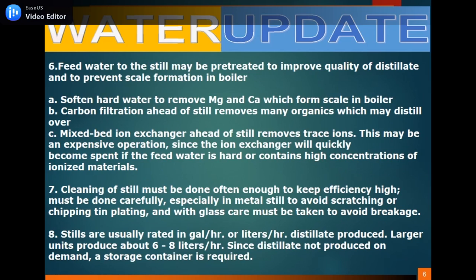Feed water to the still may be pre-treated to improve the quality of the distillate and to prevent scale formation in the boiler. Hard water should be softened to remove magnesium and calcium, which form scale in the boiler. Carbon filtration ahead of the still removes many organics which may distill over. A mixed-bed ion exchanger ahead of the still removes dissolved ions. This may be an expensive operation since the ion exchanger will quickly become spent if the feed water is hard or contains high concentrations of ionized materials.